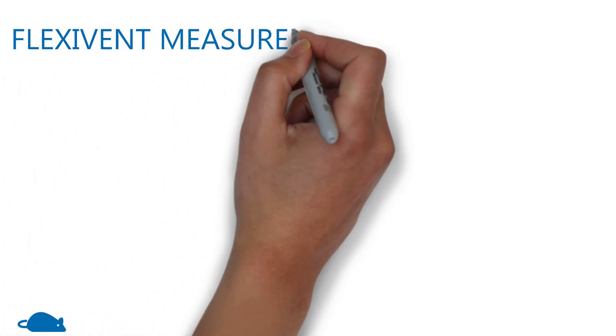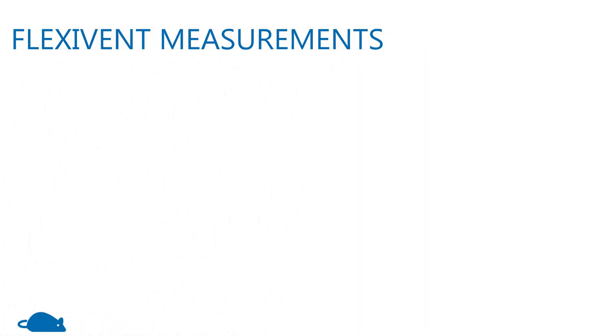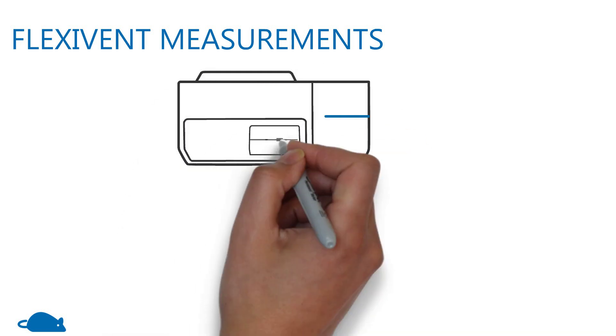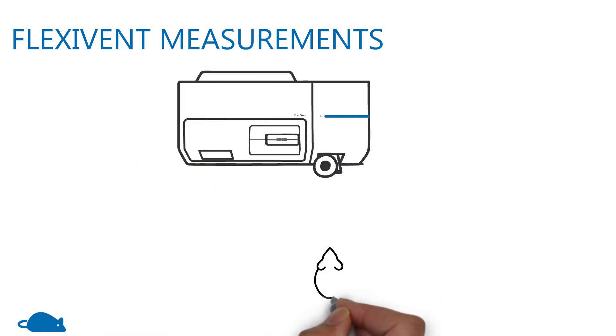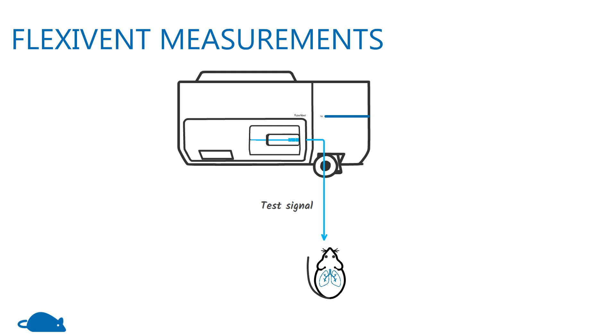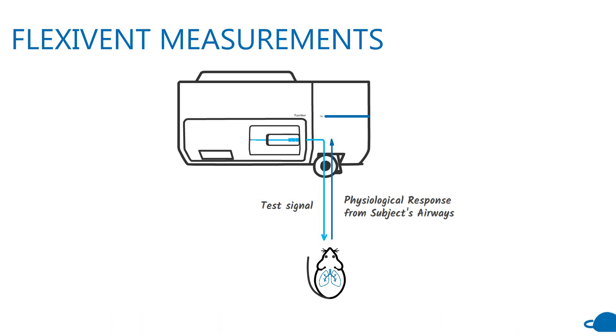The flexi-vent uses an active measurement technique. Using this technique, test signals are introduced to the subject's airways, and through changes in pressure, volume, and flow, the mechanical properties of the respiratory system can be measured.